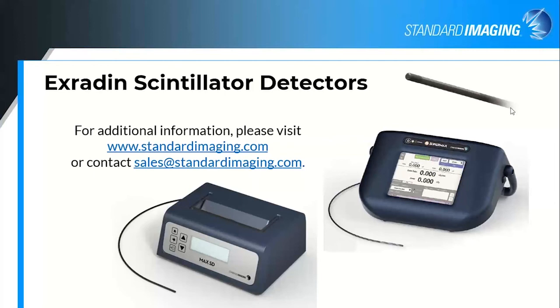Could the W1 or W2 be used for low energy x-ray dosimetry? We don't have the sensitivity in our optics for that right now because of the very small signal level we get from kV x-rays. That's not what this device was built for, and it doesn't do a very good job with that right now. If there's high interest in that, we could work on a development project, but so far there hasn't been much interest.